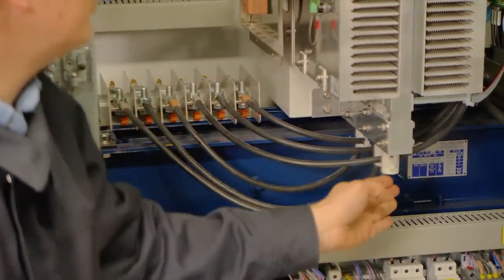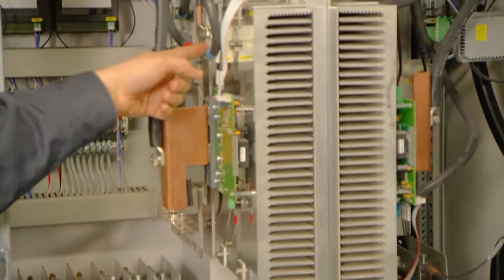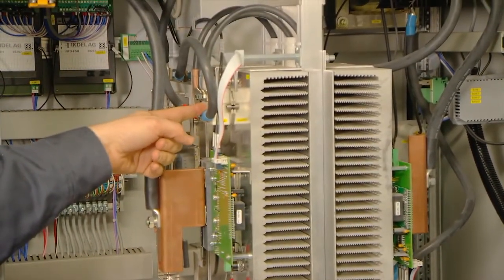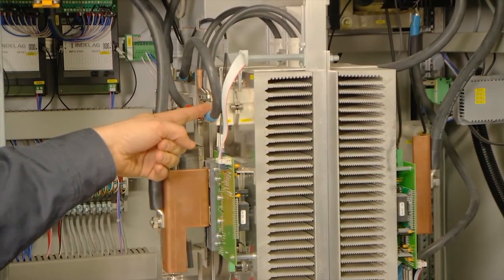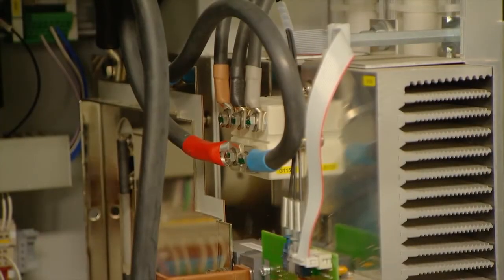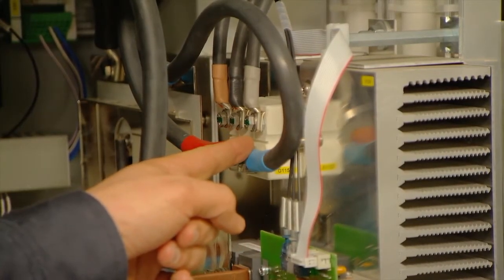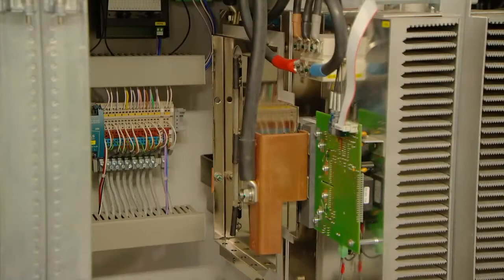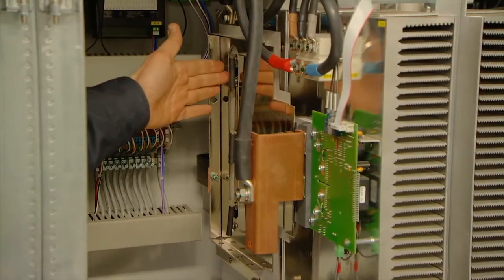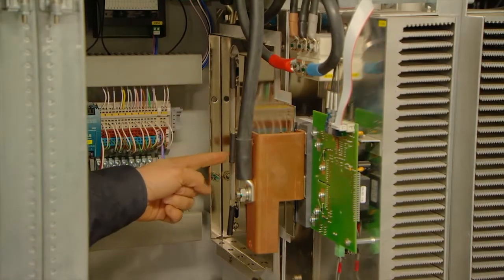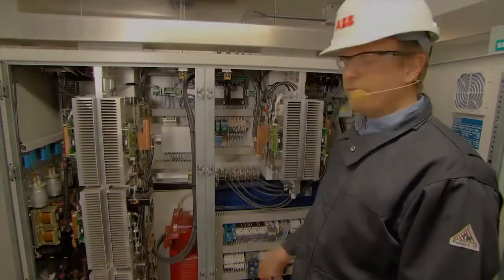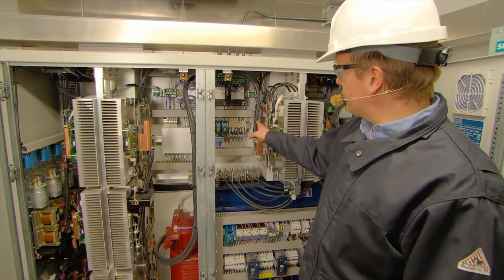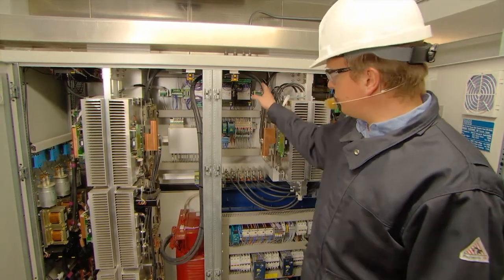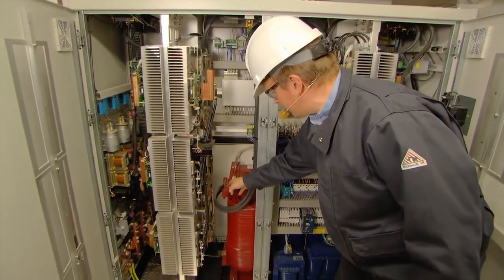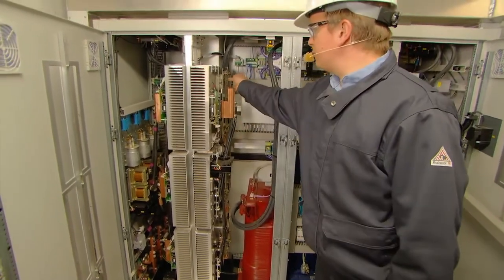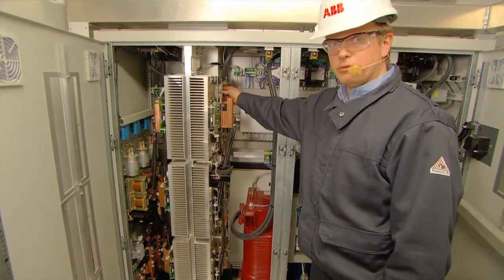From here they go up to the rectifier, which is rectifying the incoming voltage to the incoming DC link. The rectifier. Capacitors for the DC link are to be found behind and under these resistors. The input DC link of 1100 volt is transformed over this red reactance to the secondary output DC link, which is then matching the output voltage.